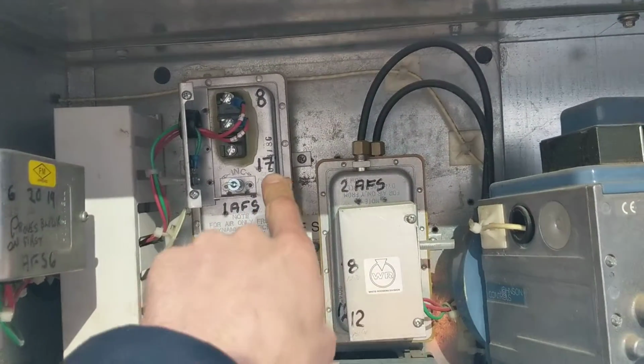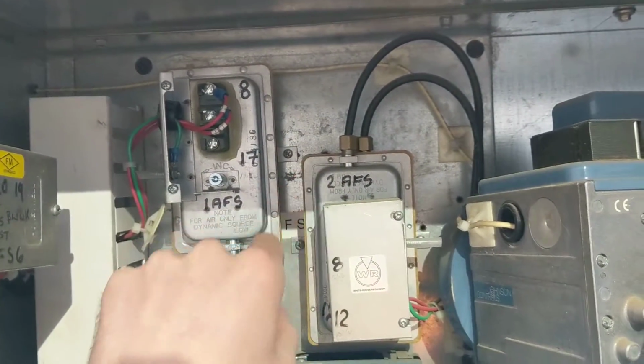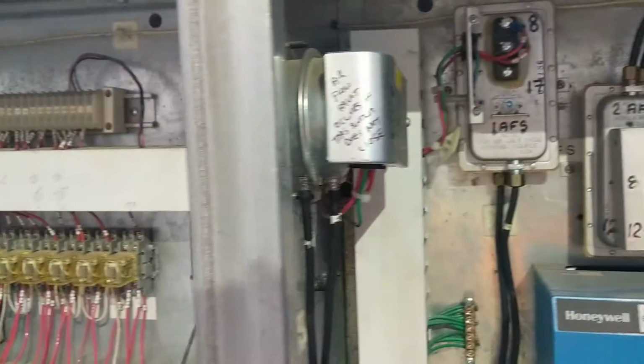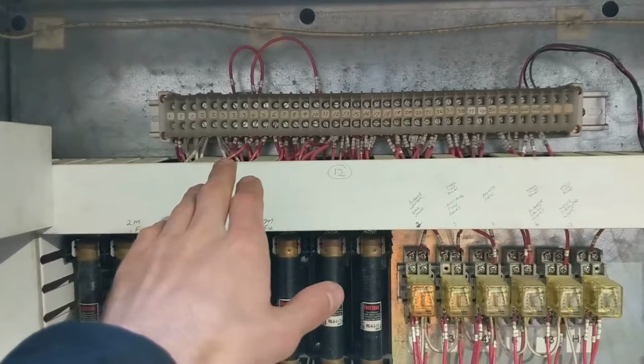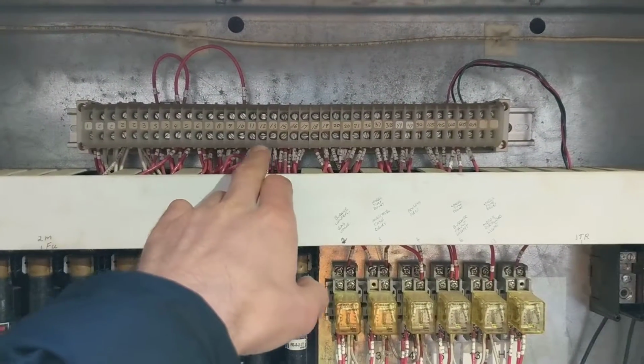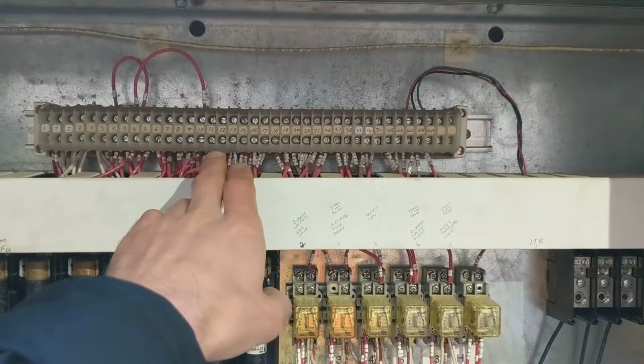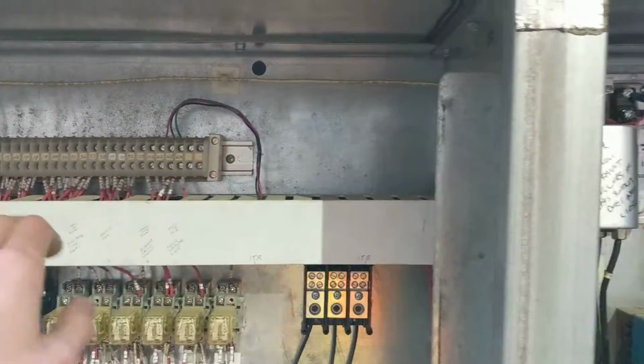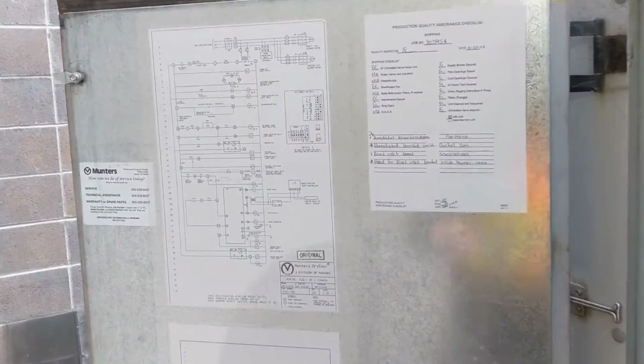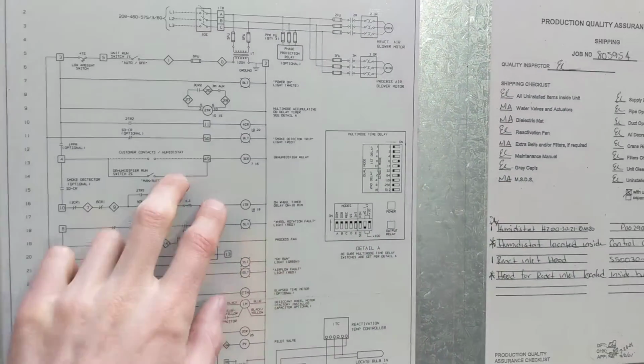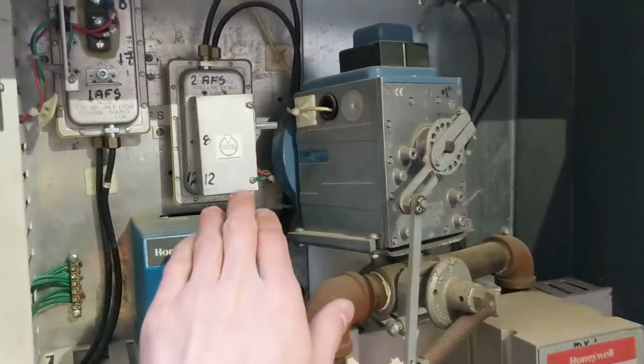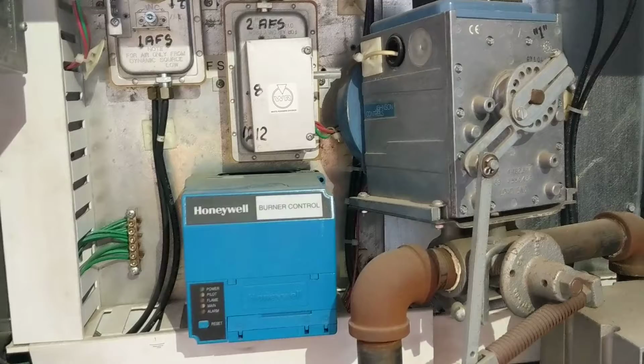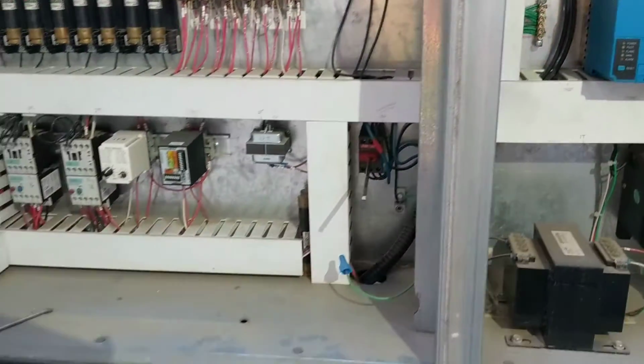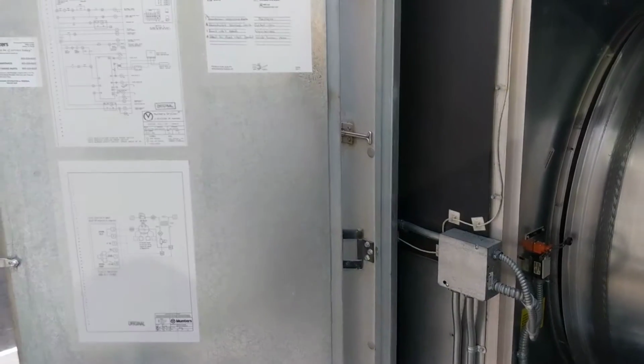Anywhere that you see numbers written on them, so 17, 8, 2, 8, 12, all these numbers correspond with where it's running in here. So if you're trying to check for power at different spots using your voltmeter, you can easily match up what's written on here with what's on here, and that also matches up with this wiring diagram here. Your wiring diagram will show anything that's not labeled. These ones have been labeled for ease of troubleshooting. Other ones that are not labeled, you'll have to reference the wiring diagram.